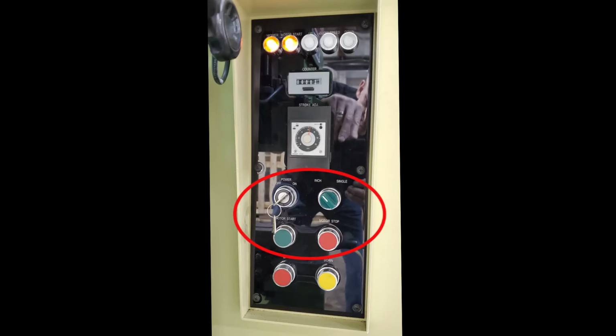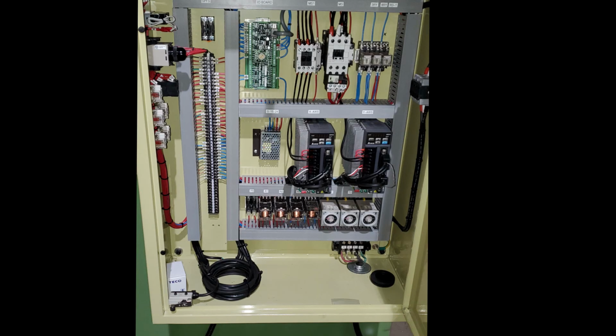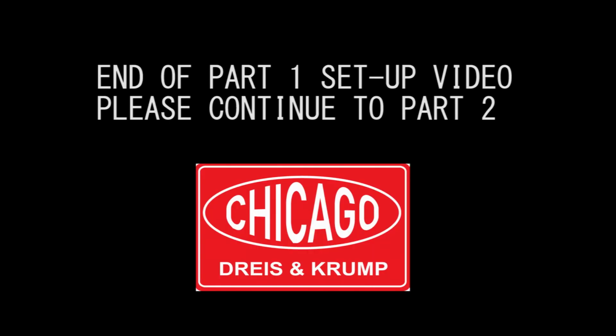In order to start the machine, turn your power on at the key, make sure you're in the inch mode, and hit the green motor button. This will just need to run for a second or two until the observer can see if it's running in the correct direction. If you find the motor is spinning in the wrong direction, you'll have to change 2 of the 3 incoming 3-phase leads, and that will get the motor running in the correct direction. At this point, your motor and pump should be rotating in the correct direction.